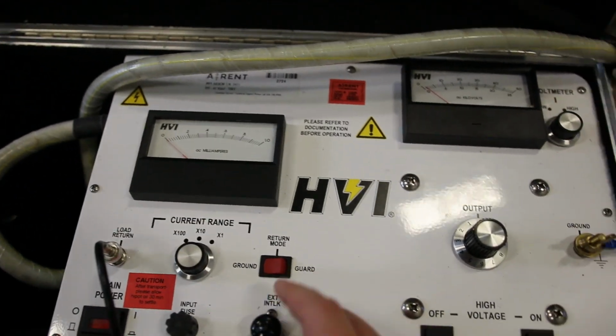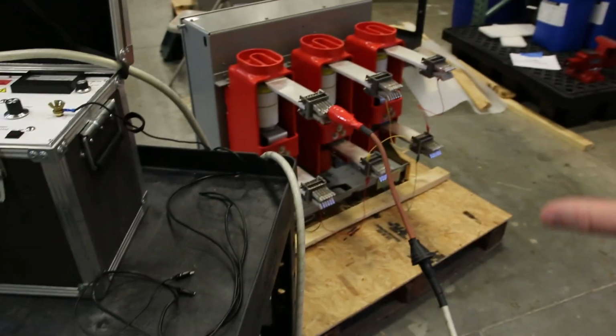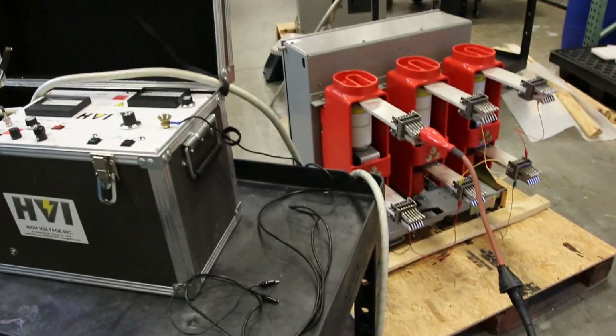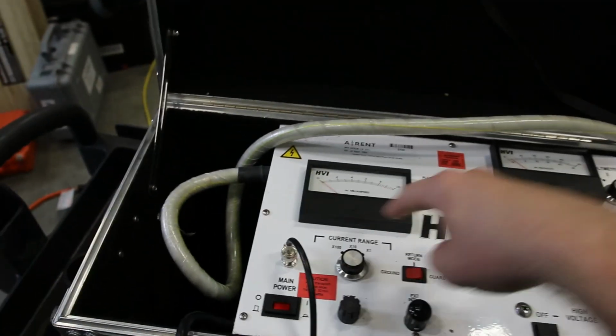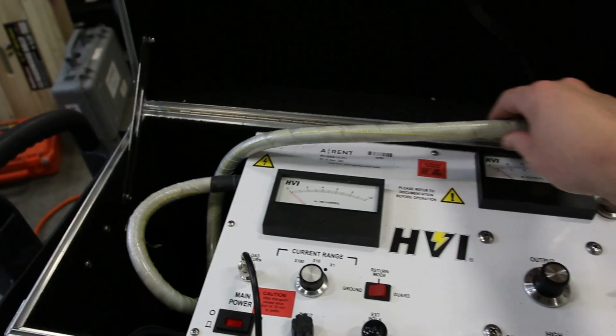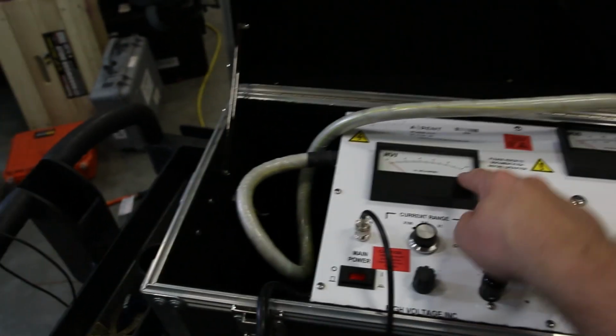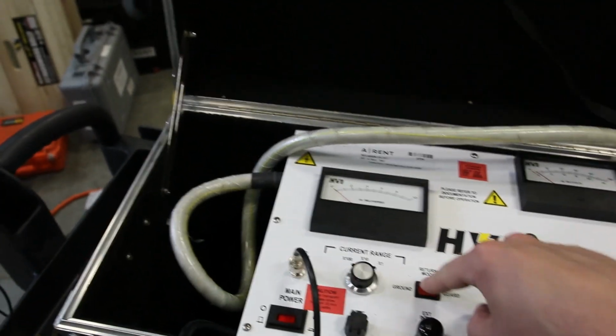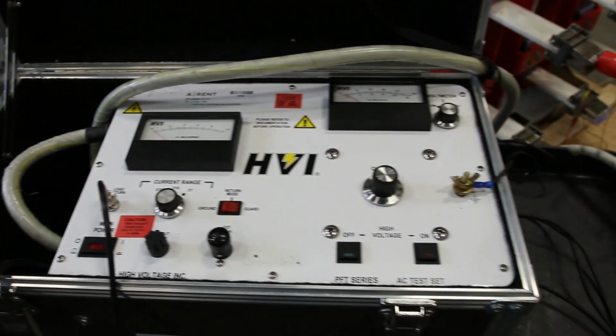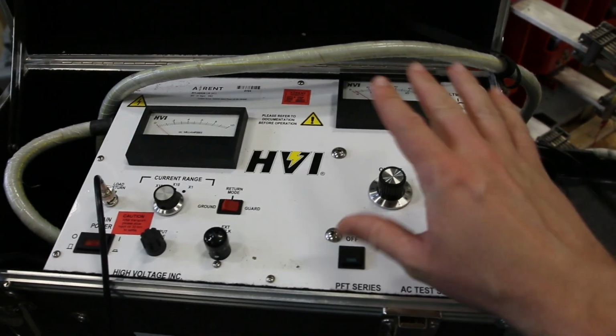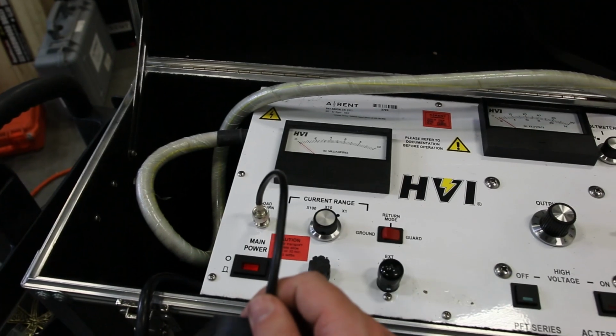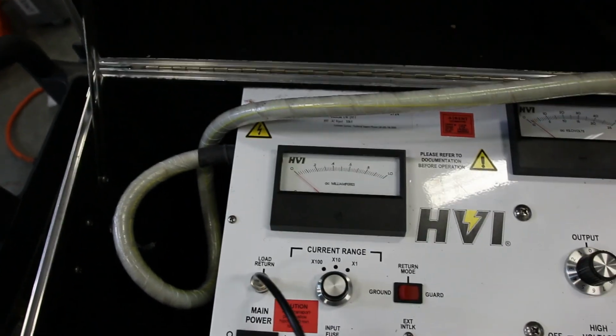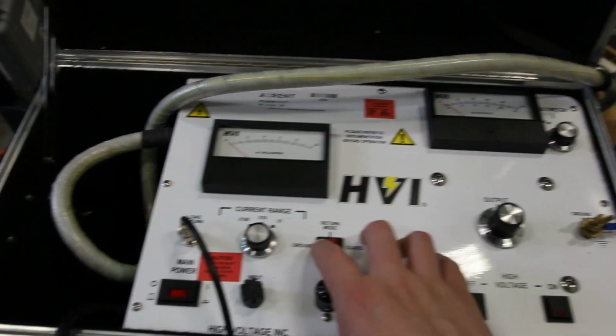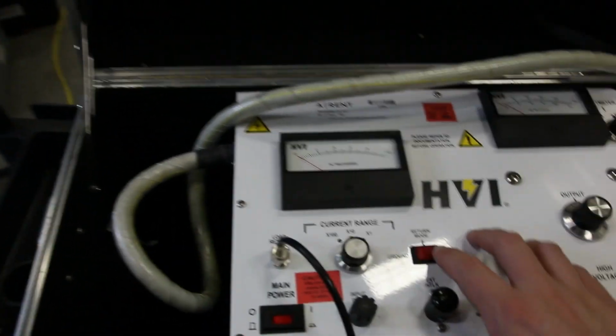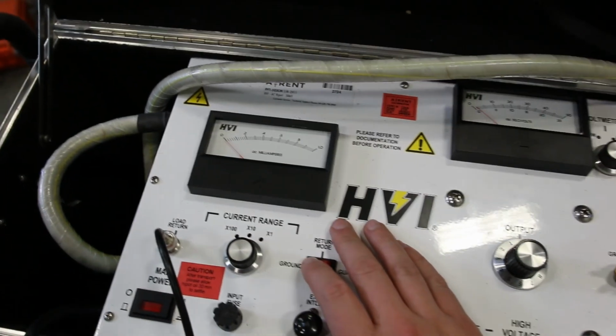We're going to be in the ground return mode because we've got everything else that we're testing, and not just the vacuum bottle, shorted to ground. The way to think about this is, if we're in ground mode, all of the current leaving the high voltage lead gets measured. We see that on the ammeter. If I'm in guard mode, all of the current that leaves the high voltage lead comes back on ground and gets ignored. Only the current that comes in the load return lead gets measured. I don't want that because I've got everything grounded. If it was on guard mode, you would get pretty much nothing the way we're configured here.